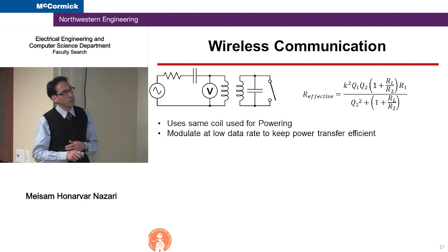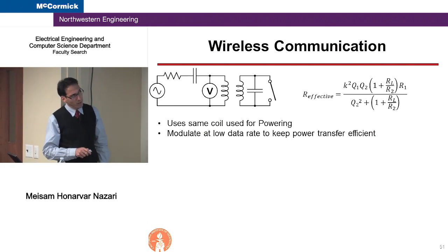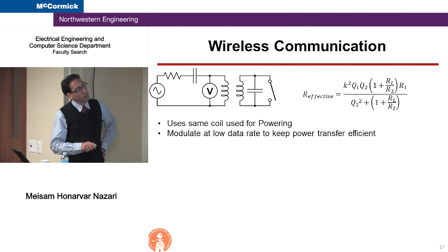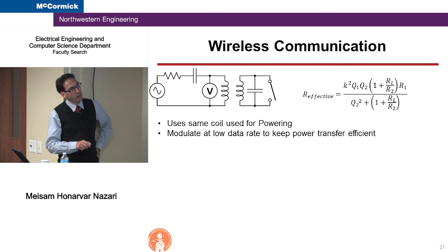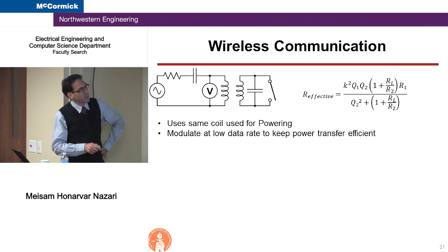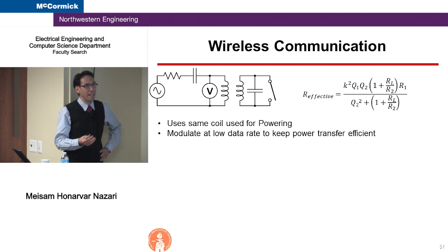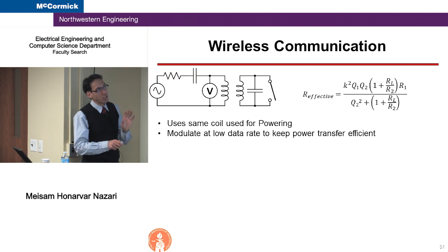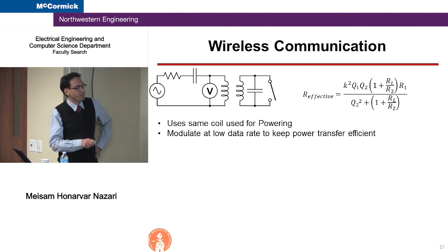So for wireless communication from the chip to the outside, as I mentioned, we are using passive RFID technology. So basically, the way it works is that if you consider a two-coil system with coupling, by changing the load at the secondary side, we are basically changing the effective resistance seen at the primary side. So when we have this coupling system, we can change the load at the implant and then be able to detect some changes in the reader. This is called in the literature load shifting or backscattering. Backscattering because we are changing the matching at the secondary side, and therefore there will be some reflection, and we are basically reading the reflection. So that's why it's also called backscattering.